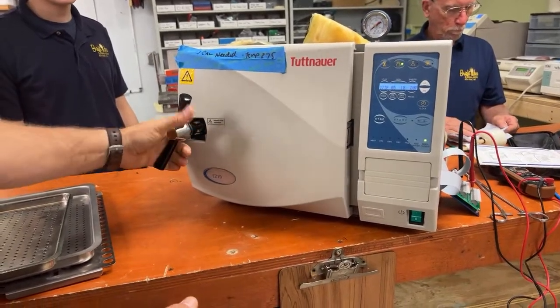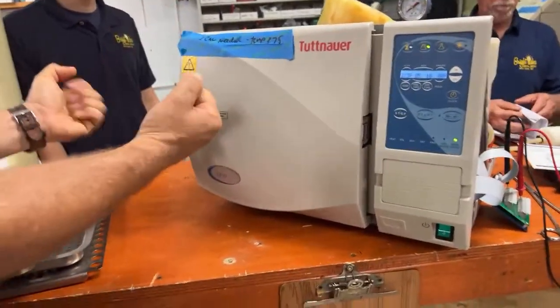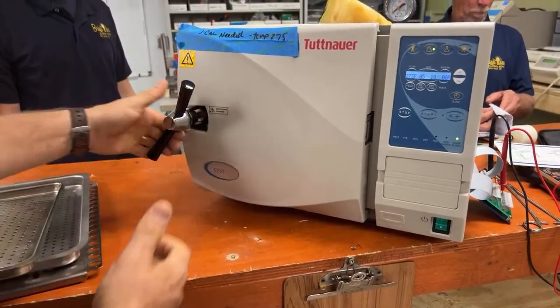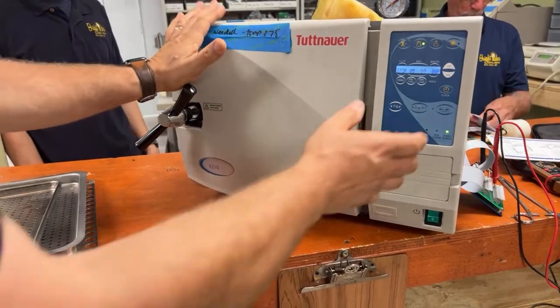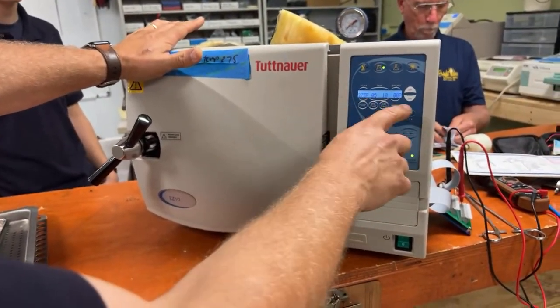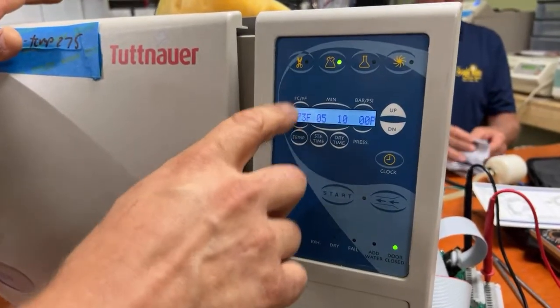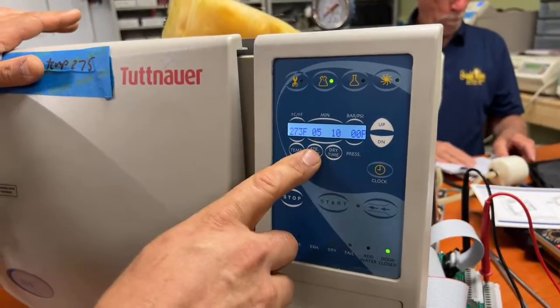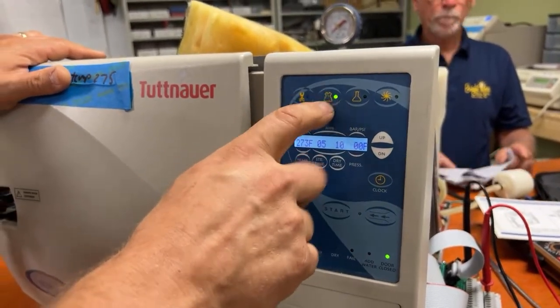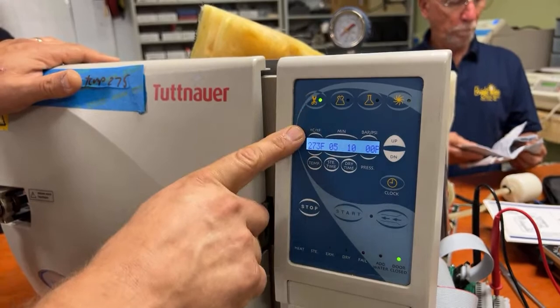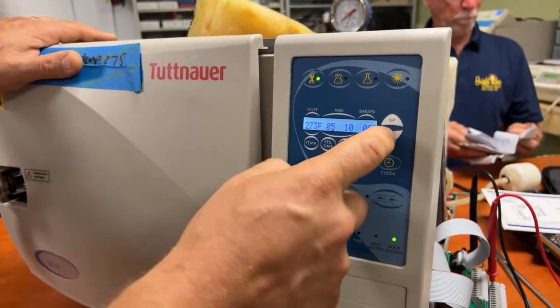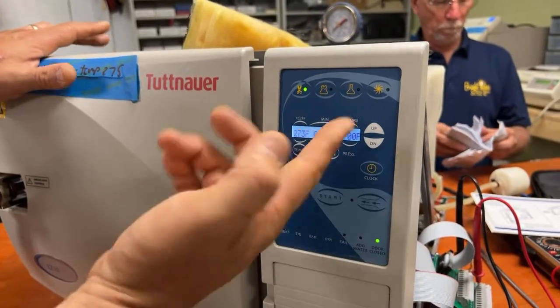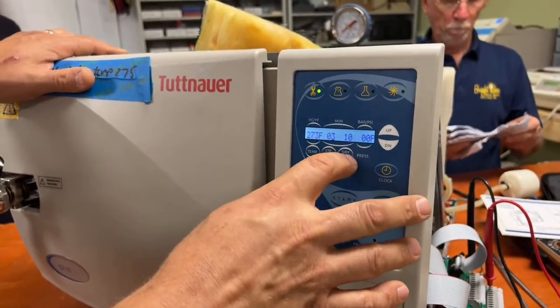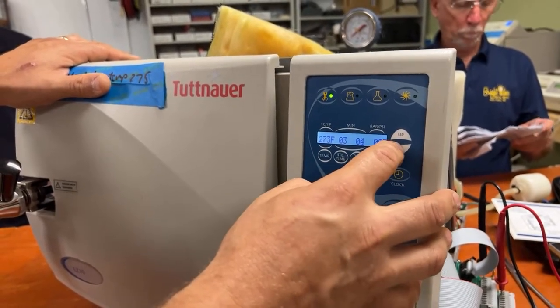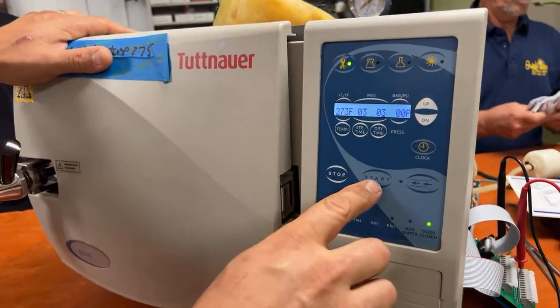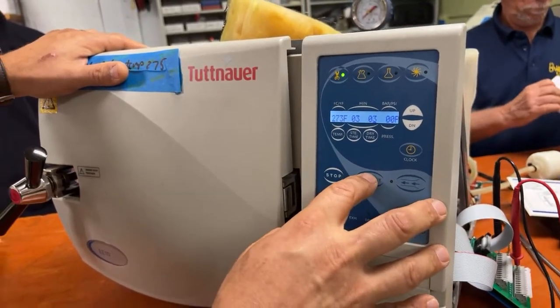All right, so when I'm closing these doors, I only ever use one hand. It has 2 handles, but I only use one because I don't want to overpower it and break it. All right, so that's good. What we're going to do is run it at what it was. So 273 is our set temperature. Sterilization time's at 5 minutes, and then dry time. And that's for this one here, which I think is pouches. We can also do an unwrapped, which if we want to adjust the time to 3 minutes, we can. So the dry time, we'll actually reduce that just so we get a quicker conclusion to our cycle. Leave them both at 3. And then we'll go ahead and hit start.